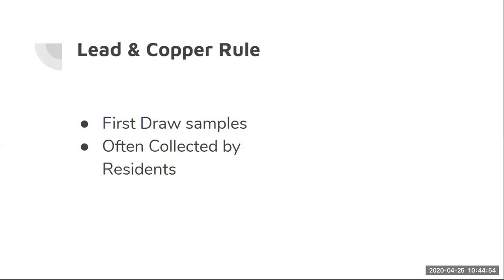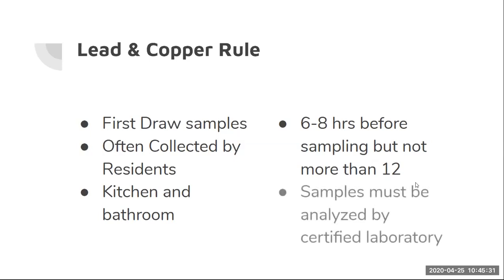So it is allowed for consumers who volunteer to collect samples. They are taught how to take a good sample. They may even be given the containers, the sample bottles, with which to do so. Before anybody uses the tap, after the water has sat in the tap overnight, the individual will take a sample. It's usually taken in the kitchen or the bathroom, 6 to 8 hours before sampling, but not more than 12. And samples must be analyzed by a certified laboratory.